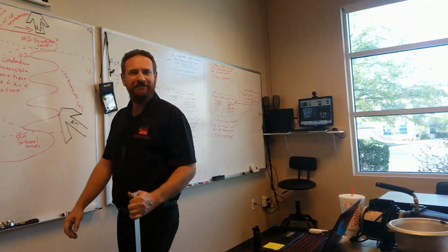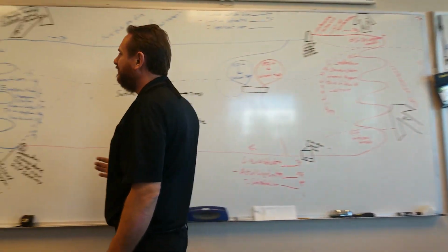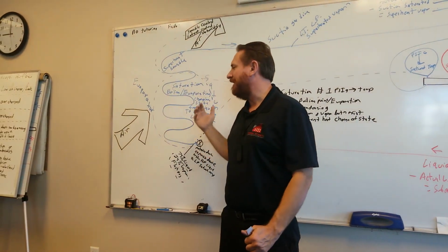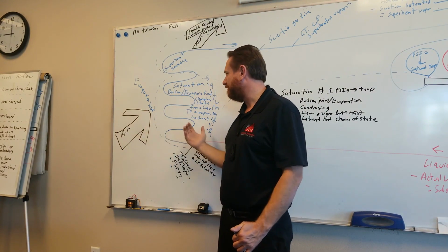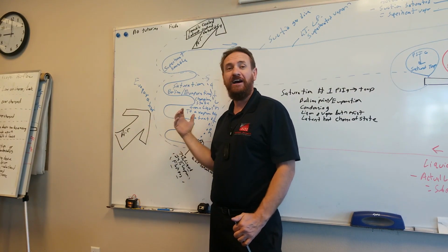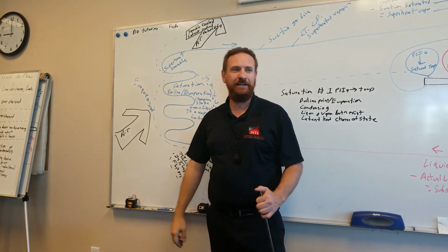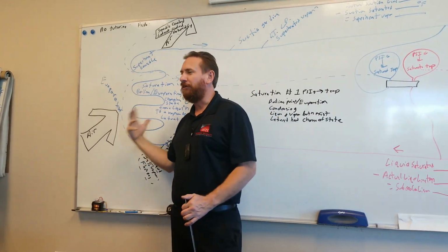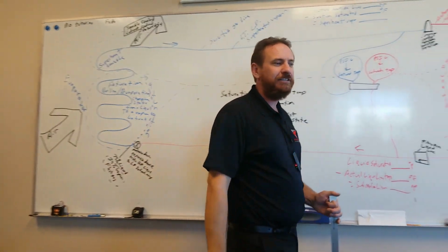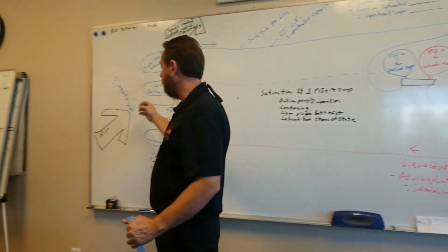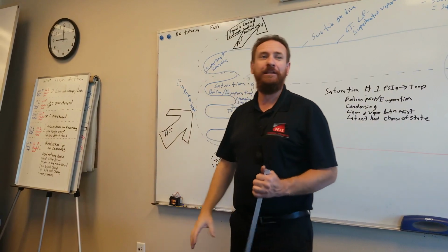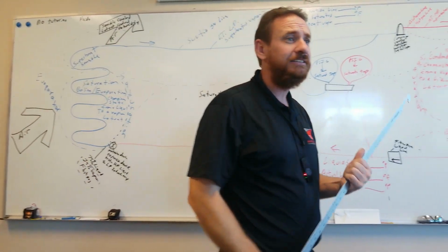To dehumidify the air, I need to move air across this evaporator at a certain rate. If I move the air across this evaporator for a certain amount of time and at a certain rate, I can dehumidify it. But if I only pull it across for a little bit and shut it off, I don't get to pull that moisture out. Plus, that evaporator coil stays moist, and that moisture is evaporating right back into the air.